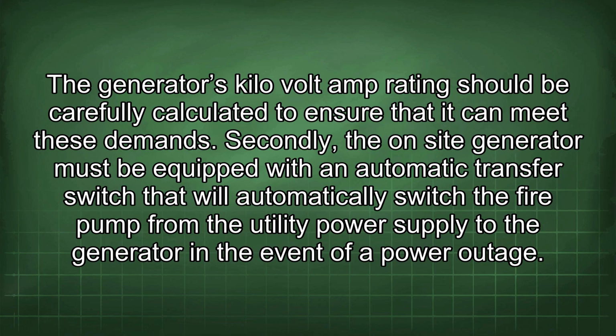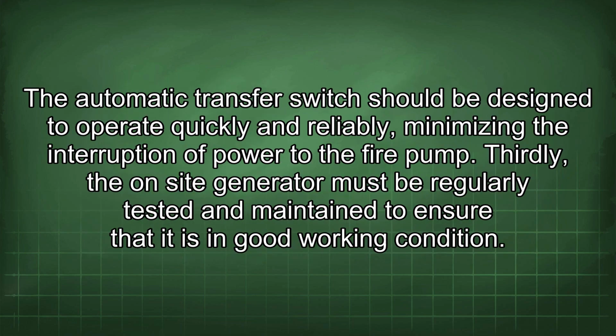Secondly, the on-site generator must be equipped with an automatic transfer switch that will automatically switch the fire pump from the utility power supply to the generator in the event of a power outage. The automatic transfer switch should be designed to operate quickly and reliably, minimizing the interruption of power to the fire pump.